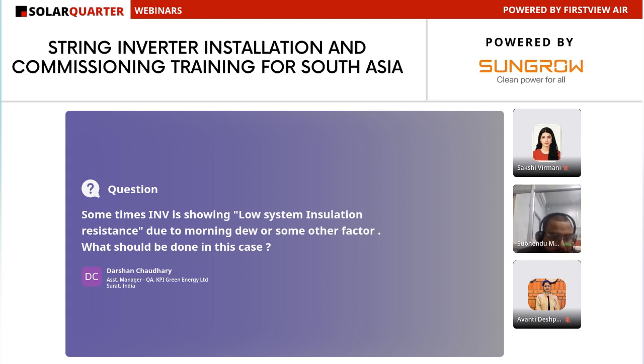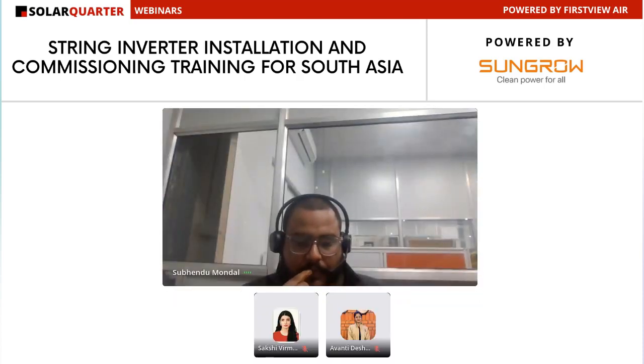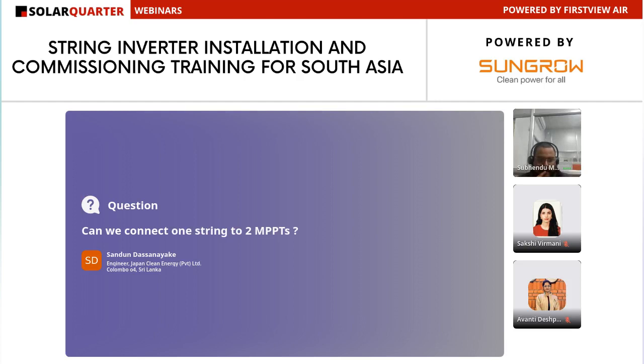Some inverters are showing low insulation resistance during monsoon. There may be some other factor. First, you have to check the string voltage and floating on the DC side. The next query is here.